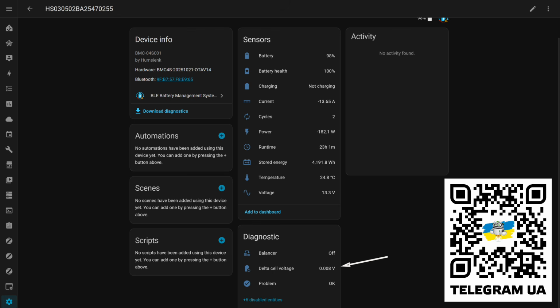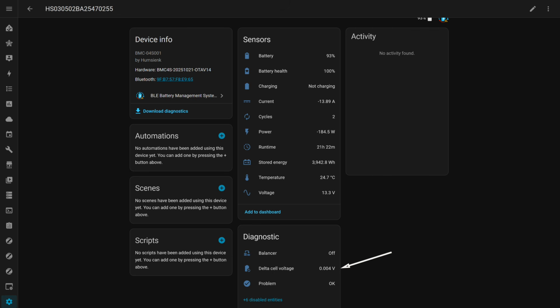Now it is 98%, and the system says that in this mode the battery can still work for more than 23 hours. After some more time, about an hour and a half later, the amount of stored energy decreased to 3.94 kilowatt hours, and the cell difference to 4 millivolts. At this point, I decided to disconnect the battery from the load and leave the tests until the inverter arrives. By the way, after some more time, already without load, the difference decreased to 3 millivolts.